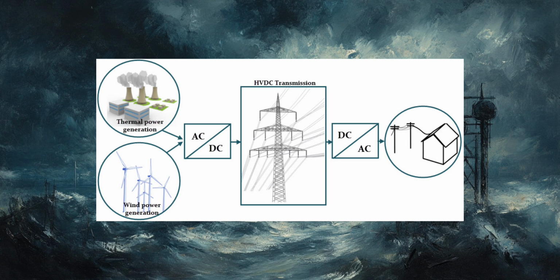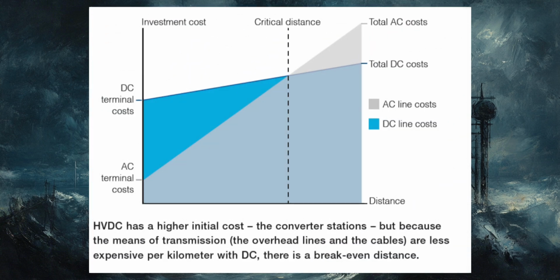HVDC takes those concepts of power conversion and applies it to a large scale. Most generating plants, with the exception of solar farms and battery storage, will produce AC power. The HVDC system will have a high-scale converter at the generator to rectify the power to DC. HVDC links provide a good solution for transmitting power over long distances. Typically, HVDC links are primarily used for very long interconnections, asynchronous interconnections, and power flow control.